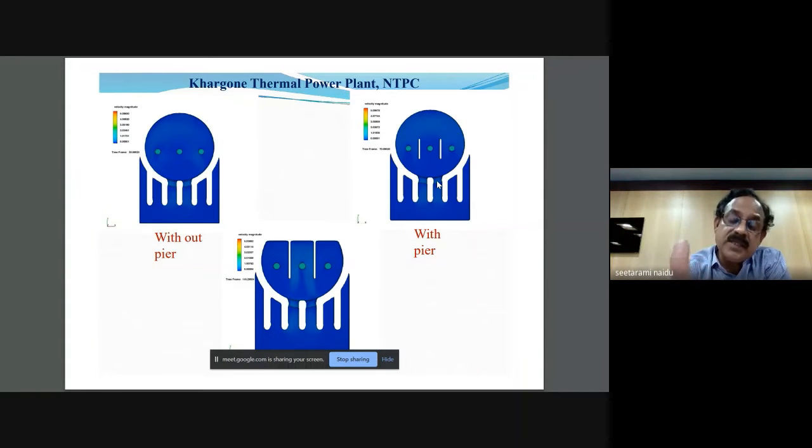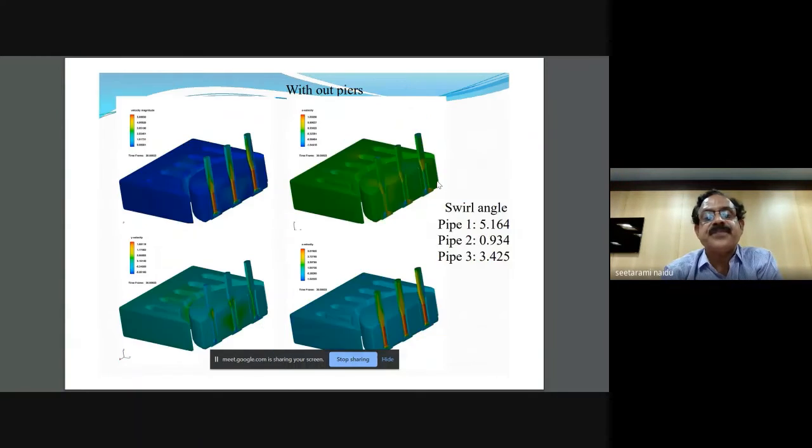Everything was done after full excavation, and they had gone too deep into excavation, and the well was constructed, the entire circular portion was constructed, then it was blanked off with a vertical wall to have a smoother hydraulic performance. So in this CFD modeling, you can see this. Then only better performance was achieved.